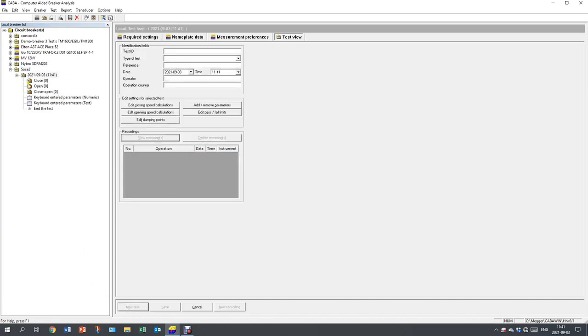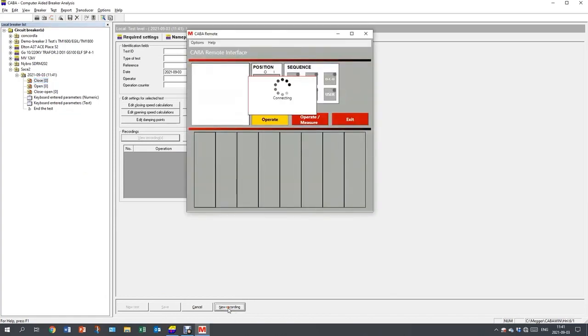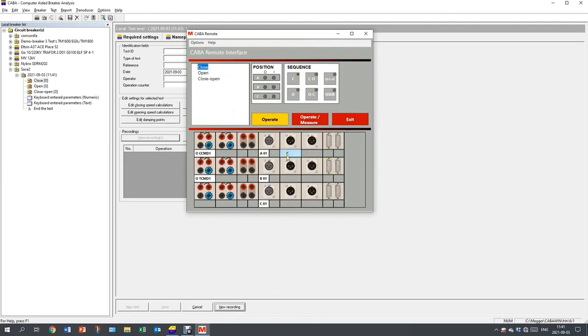To continue. And here I have my breaker in the list. I start with creating a new test and select close for the first operation. I do a new recording. And I need to confirm the motion by clicking on the flashing C for the analog channel. I'm going to do the control operation. To do the operation, you see you get a message there that you need to press control. So I press control and operate measure button. And now I'm going to get a bang.